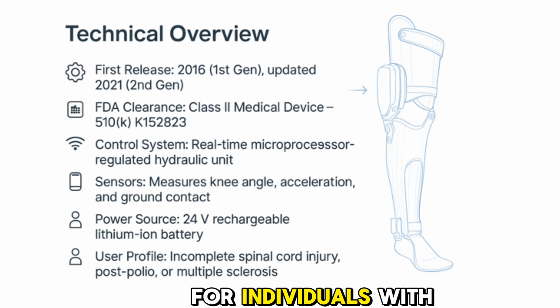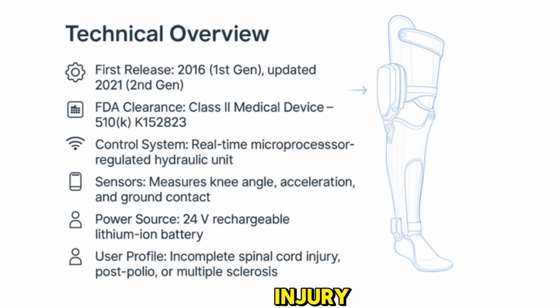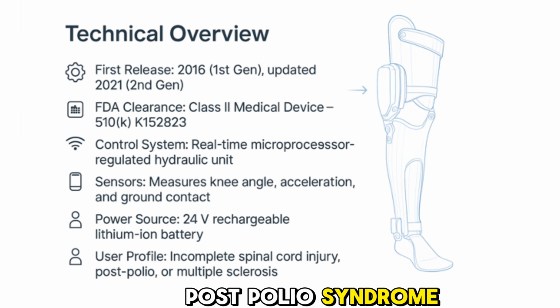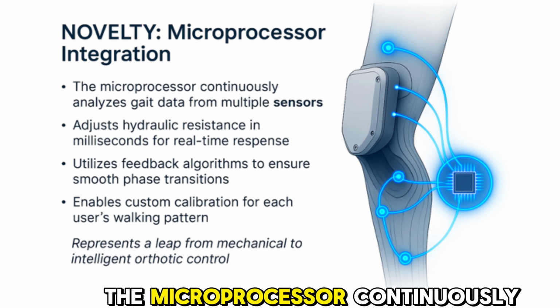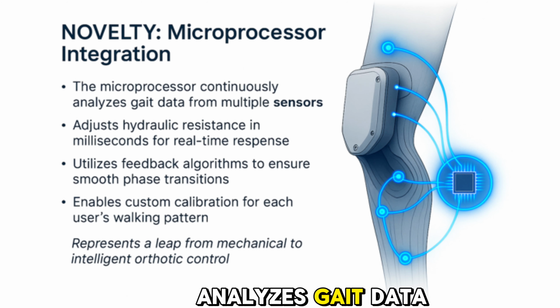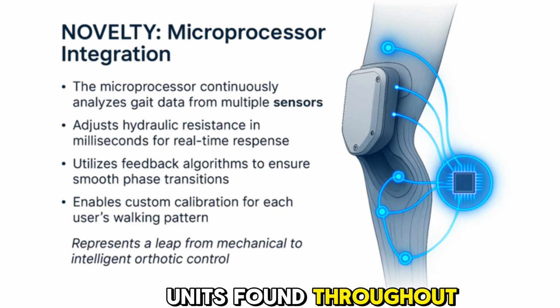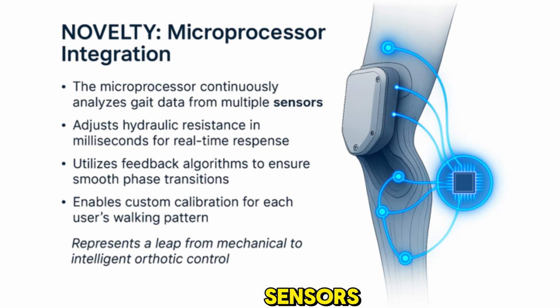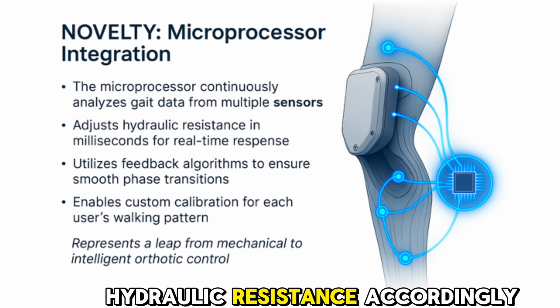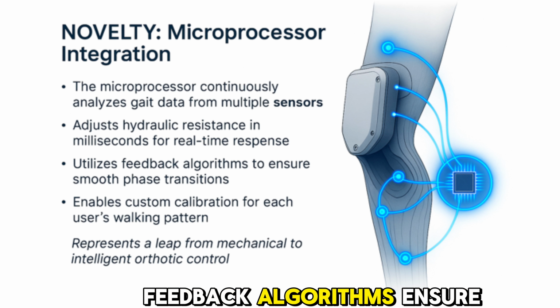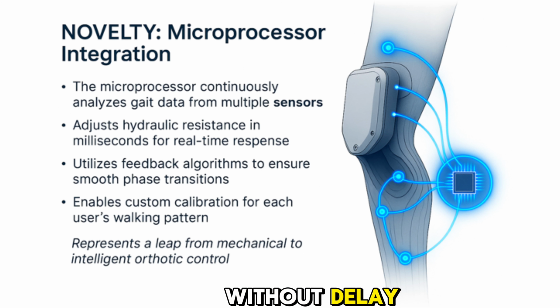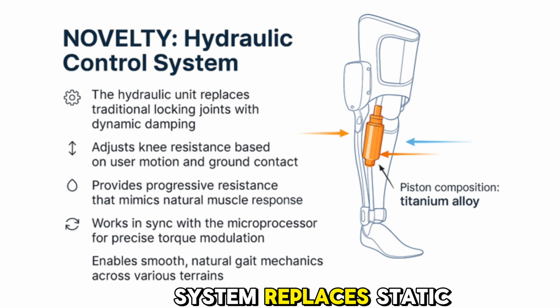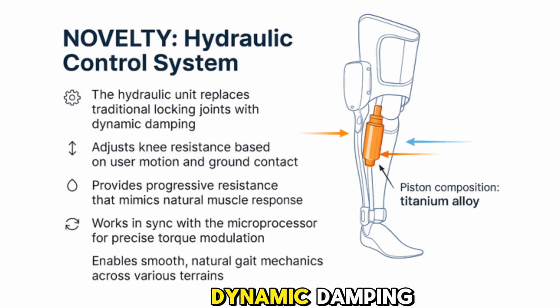It is indicated for individuals with incomplete spinal cord injury, post-polio syndrome, or multiple sclerosis. The microprocessor continuously analyzes gait data from inertial measurement units found throughout the device's multiple sensors. The microprocessor processes this data within milliseconds and adjusts hydraulic resistance accordingly. Feedback algorithms ensure phase transitions occur without delay, and calibration routines allow the device to be tuned to each user's gait parameters. The hydraulic control system replaces static locking joints with dynamic damping.